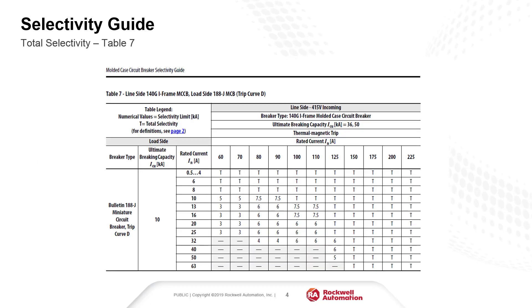Let's look at an example from our Selectivity tables. This table has a 140G IFrame Molded Case Circuit Breaker on the line side and a 188J Miniature Circuit Breaker on the load side. According to the definition for Total Selectivity, the Miniature Circuit Breaker will open without making the Molded Case Circuit Breaker trip.